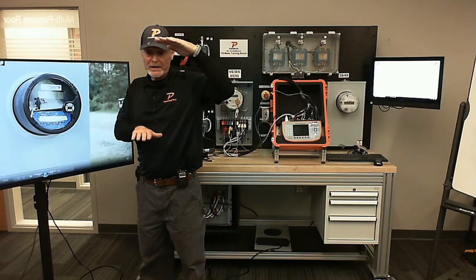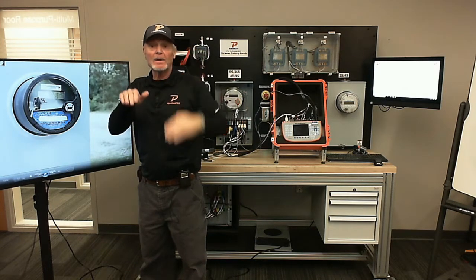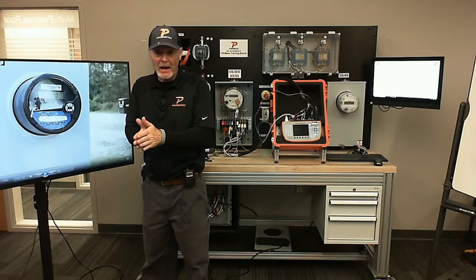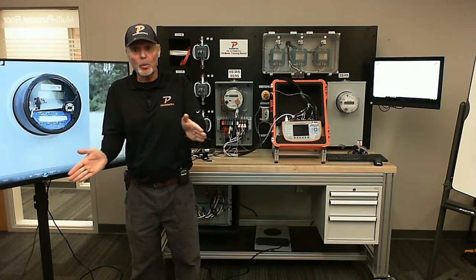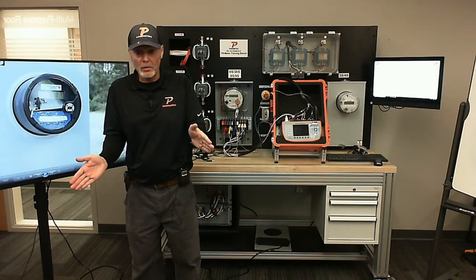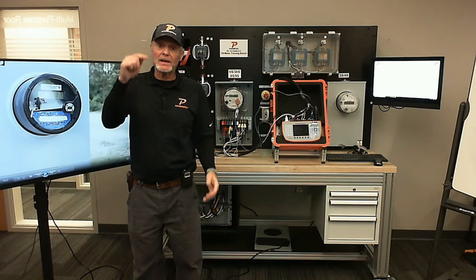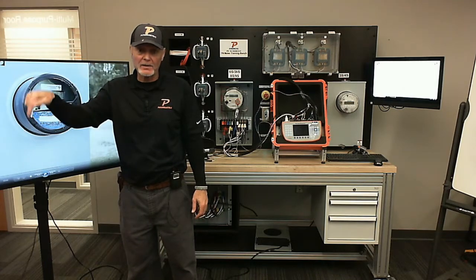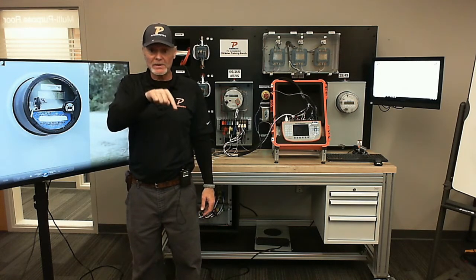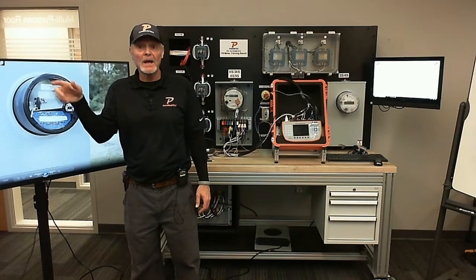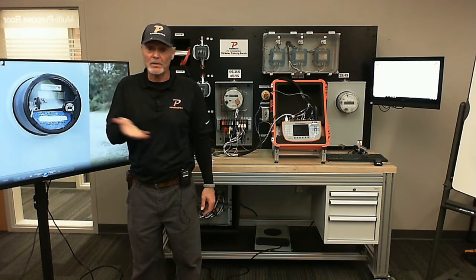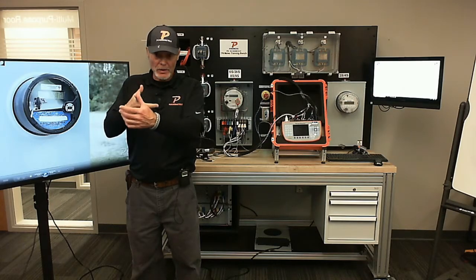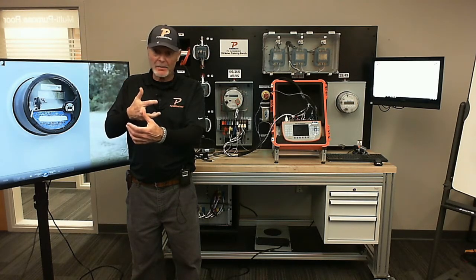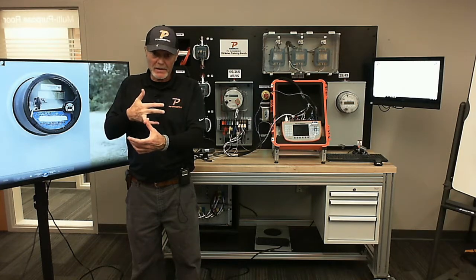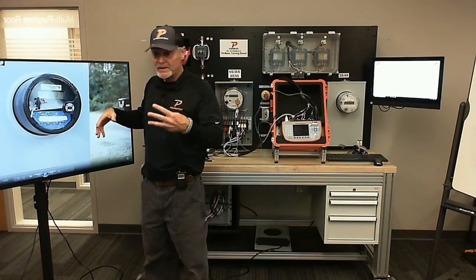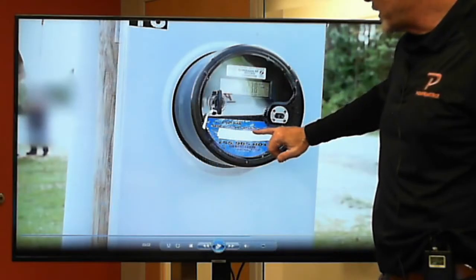So now I've got 0.25, and then my power factor is always 0.5 is what I use, which is a bad power factor, which equates to a really wide angle, a 60-degree angle, which would be horrible. You'd be losing your behind, right? Because remember, it's voltage times current times power factor equals watts. So if I took my voltage and my current and multiplied by 0.5, I'm already cutting it in half, and I'm losing half of my revenue right off the top. So you're doing a test of putting a good load on it, a really jacked up power factor, and then a very light load on there, okay? And that is that phantom load test. But you glean the full load right off the face of that meter.